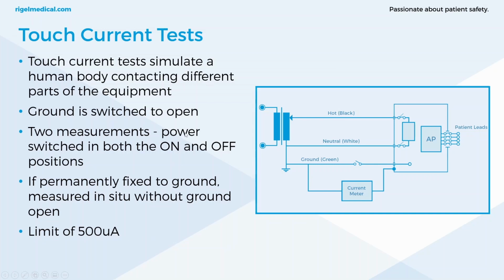Again, 2 measurements are taken, with power switched in both the on and off positions. Now, if you use an automated safety analyzer like the 288, it will come up on screen. You'll carry out a touch leakage test, and it will say turn the device on, and then it will tell you to turn the device off between each prompt. So the test sequence for NFPA 99 is already automated in the 288.